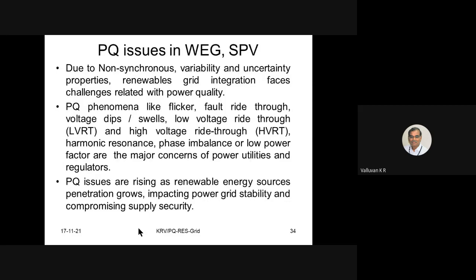Power quality phenomena like flicker, fault ride through, voltage dips, swells, low voltage ride through (LVRT), high voltage ride through (HVRT), harmonic resonance, phase imbalance, or low power factor are the major concerns of power utilities. Still, we have a regulator, we have a utility. If I am independently producing power and independently consuming power, then there is no problem, because I am not connected to the grid. But when we are connected to the grid, we have to go by the grid discipline.